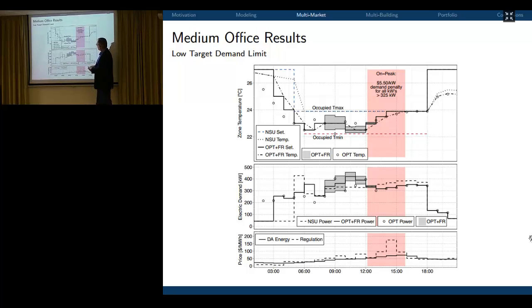Now, what you see here is the circles, which is what the building would do if it was just participating in the day-ahead market. It would pre-cool the building a little bit to take advantage of that. Now, if I combine day-ahead and frequency regulation, I get this black line plus the gray box around it. So these are the set points and the variations in temperature that I allow to provide a certain electric demand variation. So these gray hours are hours in which I take advantage of the day-ahead energy as well as the frequency regulation pricing. So if I jointly optimize both markets, why isn't anything happening here in this period?